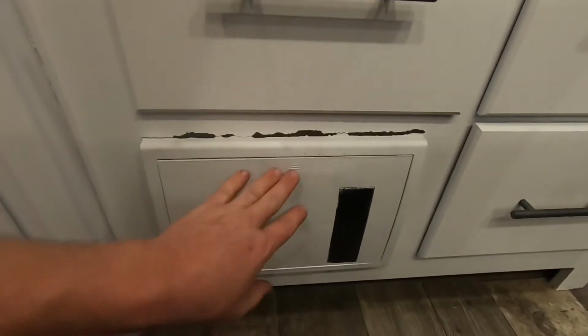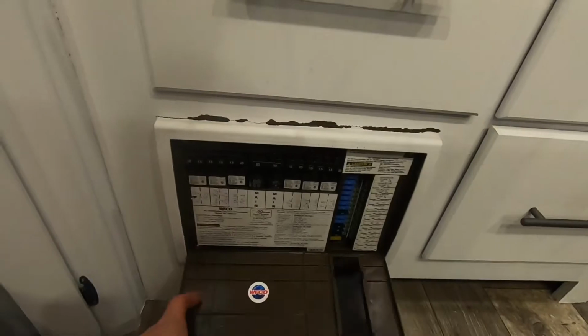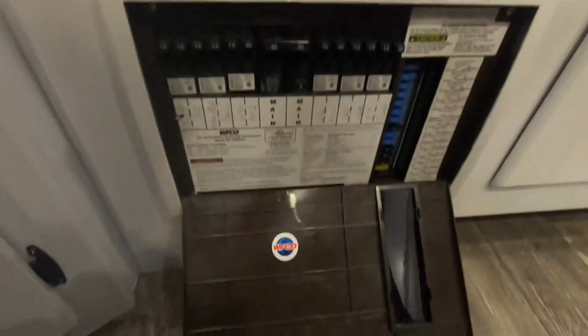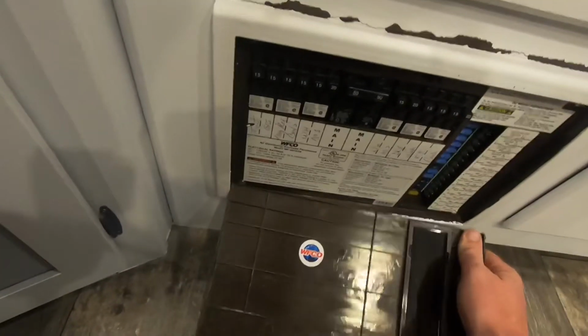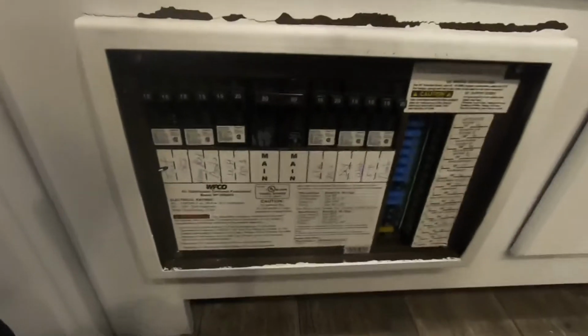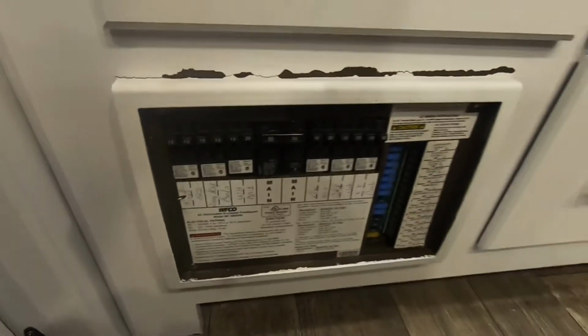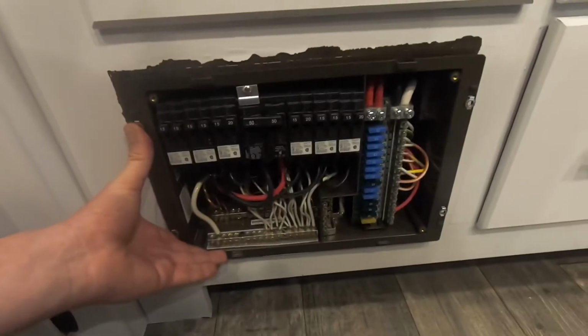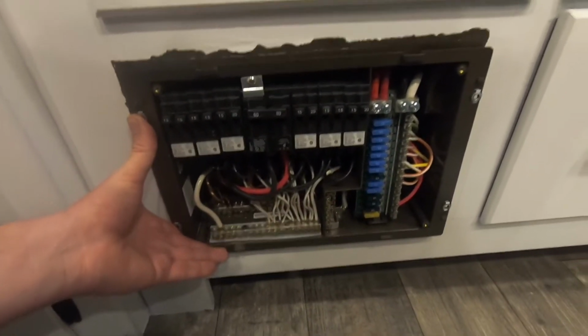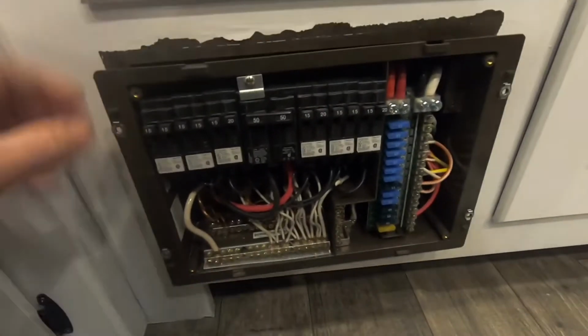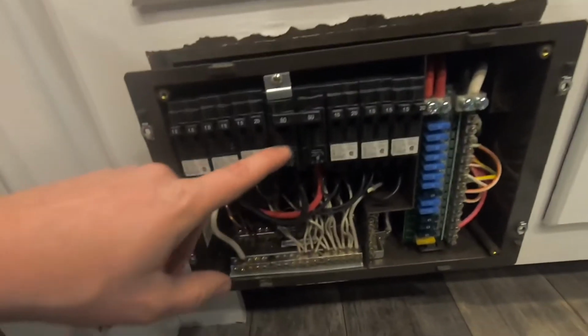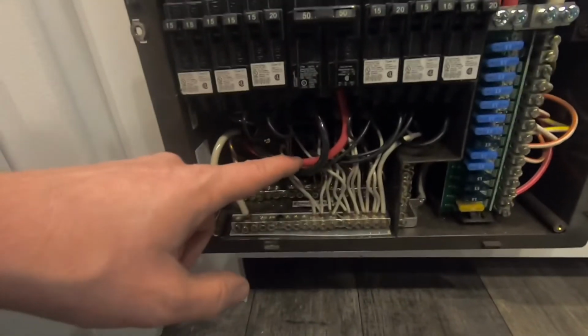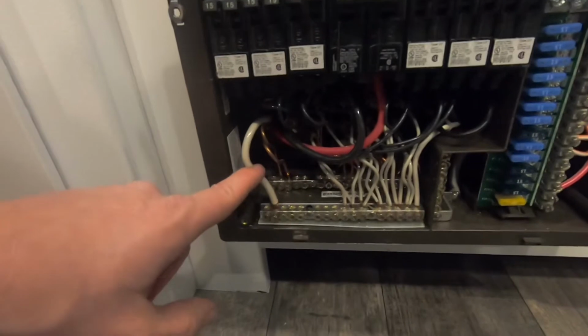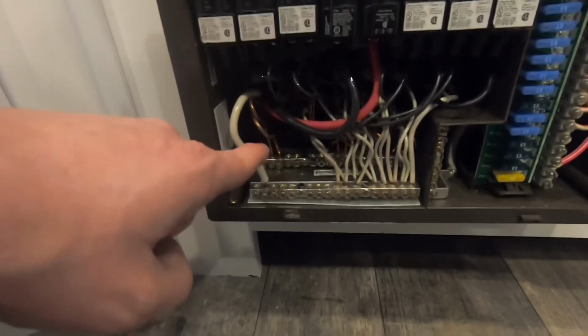So here's the 50 amp AC panel with all your breakers. To get this out, you simply take the cover off. There are 4 machine screws that hold this in. Once you get this plate out, there will be 4 more wood screws. Now that all 4 wood screws are undone, and double checking the power is off, this is where it slides out. These are your 2 50 amp poles, here's your lead 1, lead 2, neutral, and one of these is your ground.